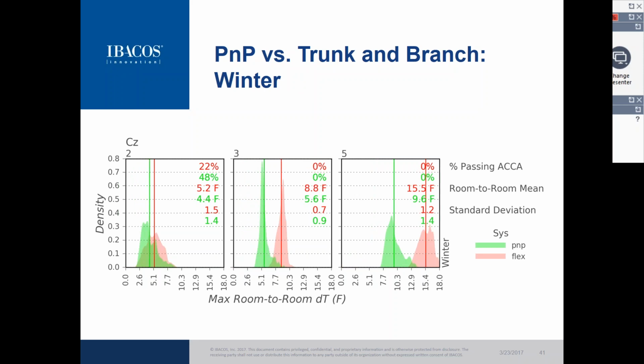In each of these three climate zones, the plug-and-play does actually better than the trunk and branch. Now looking at the winter, we did not include any balancing difference between the two seasons. The simulations included the same airway sizing for each season, and because cooling dominated, the winter season saw much worse comfort. However, when comparing the plug-and-play to the flex system under the same level playing field of no balancing dampers, the plug-and-play also exceeded the performance of the traditional system.